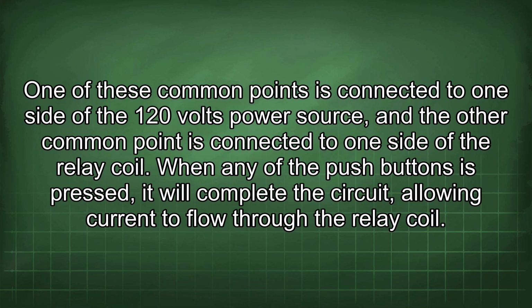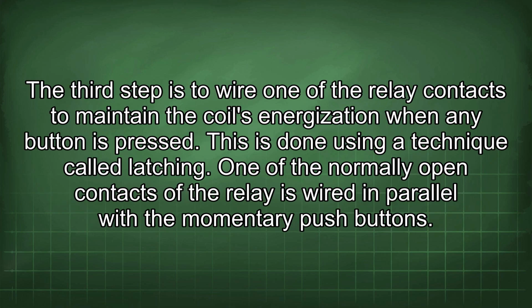When any of the push buttons is pressed, it will complete the circuit, allowing current to flow through the relay coil. The third step is to wire one of the relay contacts to maintain the coil's energization when any button is pressed. This is done using a technique called latching.